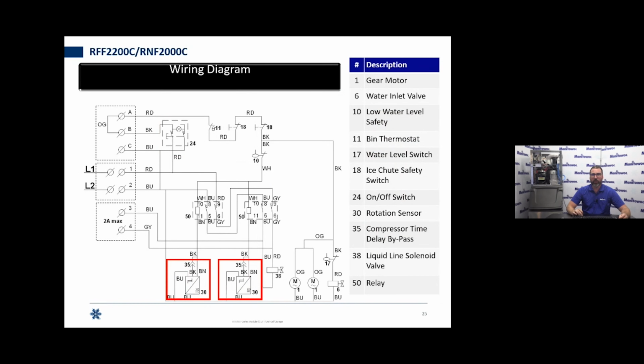Now, I'll also point out that on our largest machine, here we show an RFF 2200, RNF 2000. Here we can see that we have 2 evaporators on this machine. And of course, because we have 2 evaporators, we're going to have 2 rotation sensors. They're going to be wired in series, doing the same thing. We just have to make sure that both see RPM before we can engage that liquid line solenoid valve relay. So they're wired in series together.